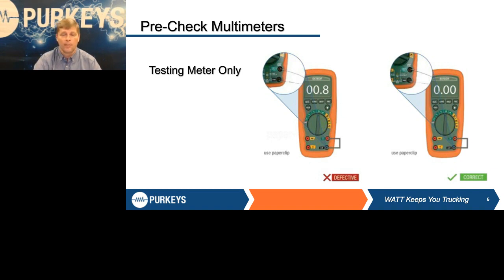The nice thing about buying a quality meter is if they do get out of calibration, you can send them in and get them calibrated and make sure it's right. What do you do with a torque wrench once a year? You send them in and get them calibrated so you know you're using a calibrated, accurate piece of equipment. But again, go through, check it. If it zeroes out, hey, my meter is good, I can move on. If not, you've got to send it in. Also, people tell me, well, I just subtract whatever the difference is. I'm not sure that's a real accurate way to do it.